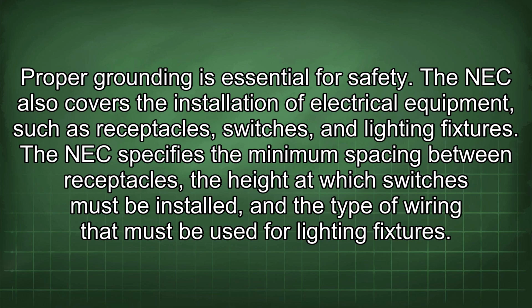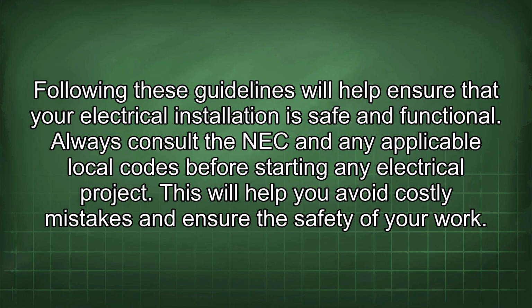The NEC also covers the installation of electrical equipment, such as receptacles, switches, and lighting fixtures. The NEC specifies the minimum spacing between receptacles, the height at which switches must be installed, and the type of wiring that must be used for lighting fixtures. Following these guidelines will help ensure that your electrical installation is safe and functional. Always consult the NEC and any applicable local codes before starting any electrical project. This will help you avoid costly mistakes and ensure the safety of your work.